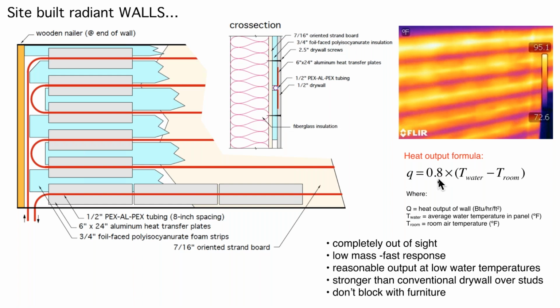So one of the things I really like about radiant ceilings and radiant walls is you don't necessarily have to cover the entire surface with tubing. You might find that you can get enough heat output, especially in a low energy building. You might only have to cover a certain amount of the wall or ceiling with this type of construction, so that reduces the amount of materials. Now, having said that, the more surface area you do create, the lower the water temperature is going to be, and that is going to reflect on the performance of the heat pump.